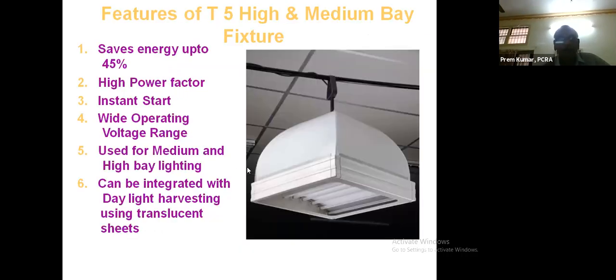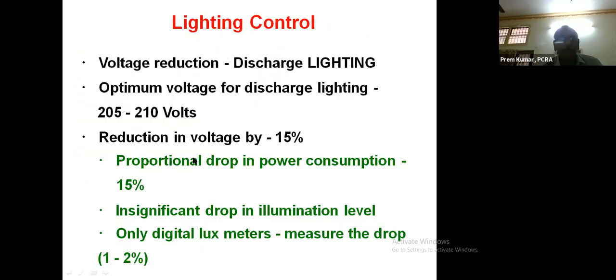These are some of the case studies where a T5 fitting replaced the high bay fitting. So lighting control is very important. It is recommended to have a separate lighting distribution transformer. With discharge lamps, we can reduce the voltage. With LED, this is of no use. This measure will become obsolete.